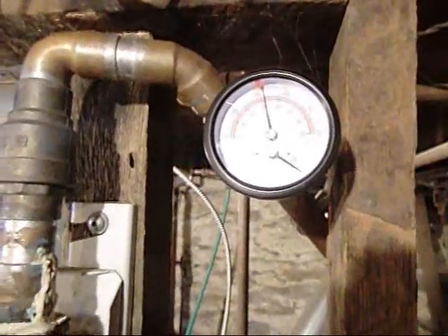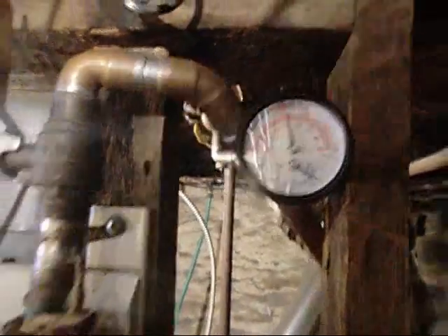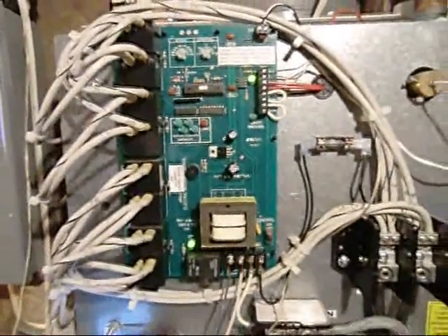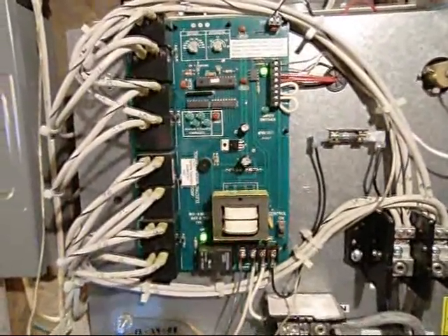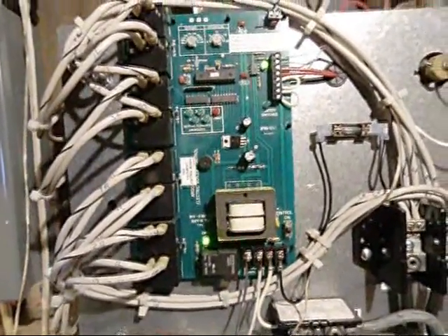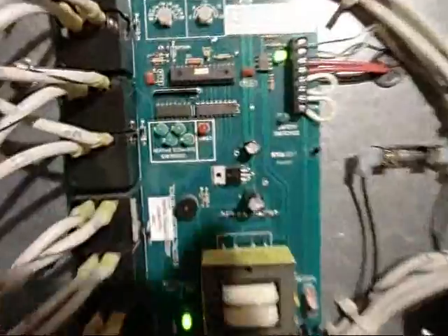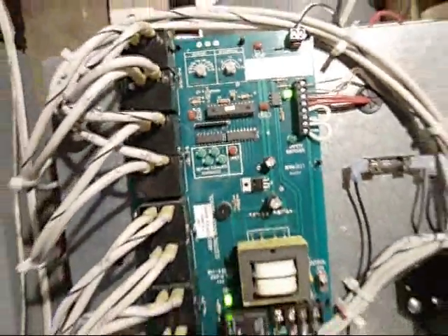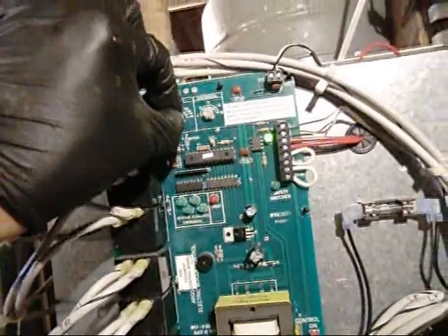(180 Fahrenheit, 84 degrees Celsius). Been standing here for an hour trying to figure out what the beeping was coming from. Fault switch. The over limits are a little over anxious. It's cold outside and it should have beeped because it just shut off. There it is. That's the problem. I got this set too high. I'm gonna lower that.